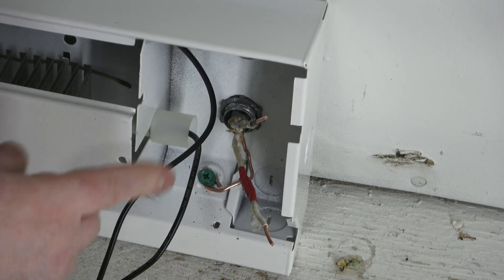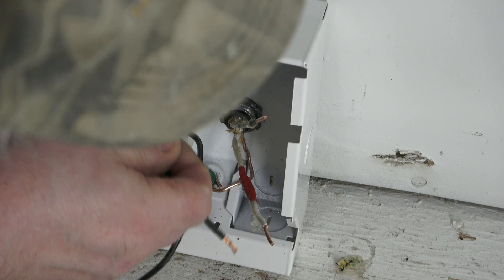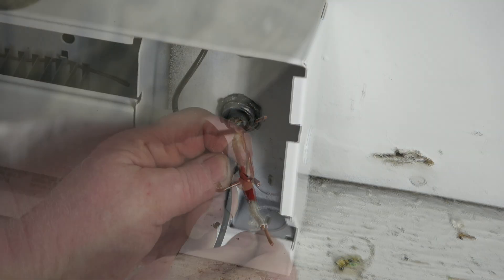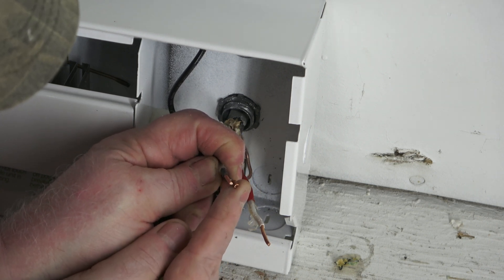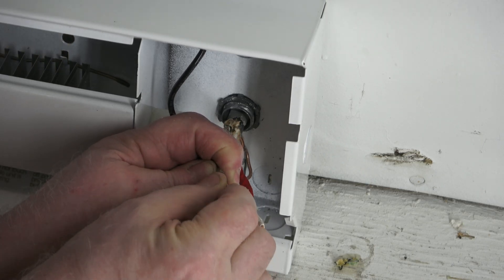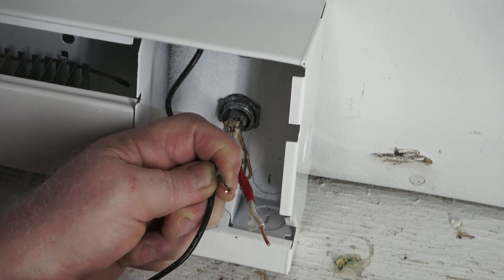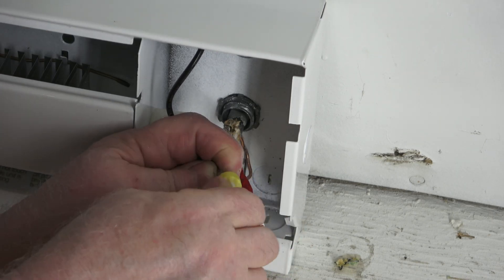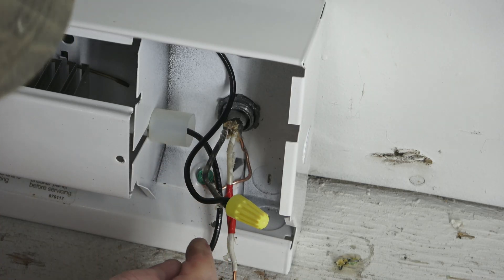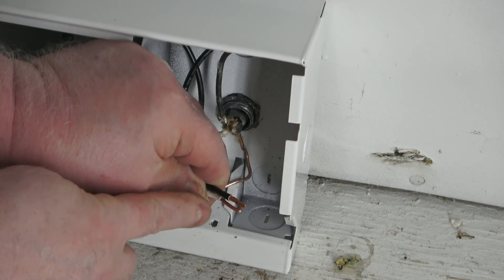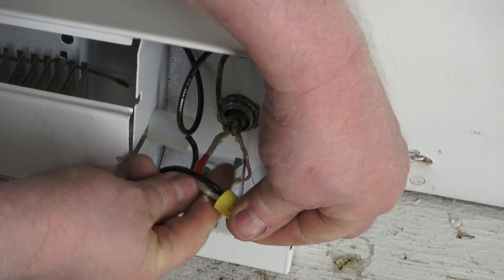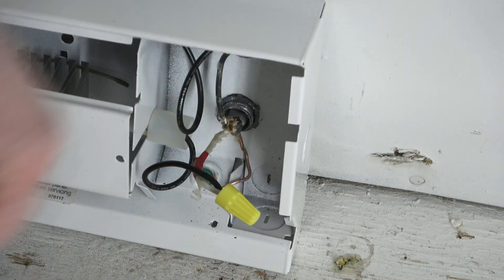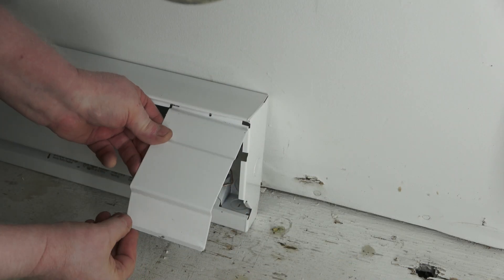So you got red and black, or black and black. So color doesn't matter which wire goes where to make this connection. So we've got a braided wire and a solid wire. With the braided, I always protrude a little bit further than the solid because the wire nut tends to push it down. And you want it close when you put it on. Or wrap just a little bit and screw it on. Allow it to pull itself on. Don't push down. You want that nice and tight. Now wrap it with tape if you want extra security. Protrude just a little bit. Let it draw on. Also another check. Hold the cap. Pull each wire. If it's not secure, one wire will pull out. Now wrap it up.